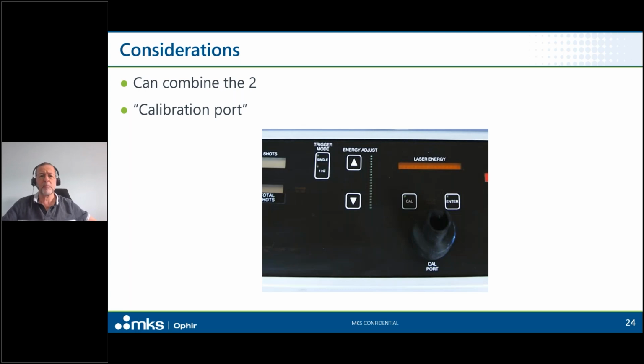This is a side panel of a laser-based medical system, and there's an opening in the side panel called the calibration port. Inside that is a fully calibrated full power sensor. And periodically, either before each procedure or once a day or whatever it may be, the doctor will take the handpiece of the laser system, stick it into the cal port, fire the laser. The system will look at the readout that it's getting from that sensor, compare it to the power or energy or whatever that it was expecting based on the electrical set and the software settings inside the system. And if needed, it'll automatically make its own internal adjustments. And then the rest of the time, a small photodiode perhaps might be monitoring the power near the laser just to catch small changes during the course of the procedure.